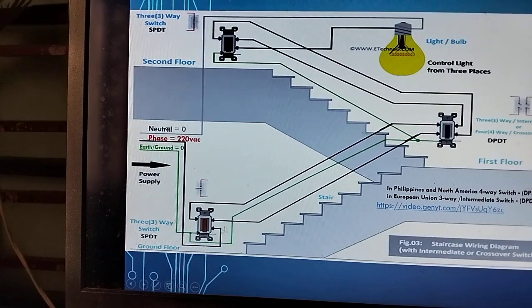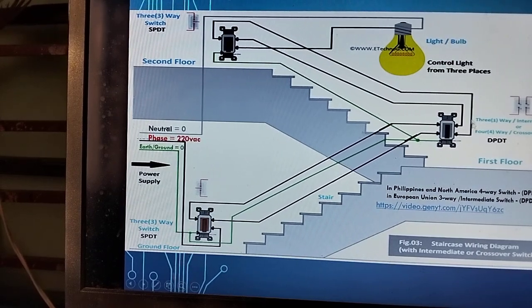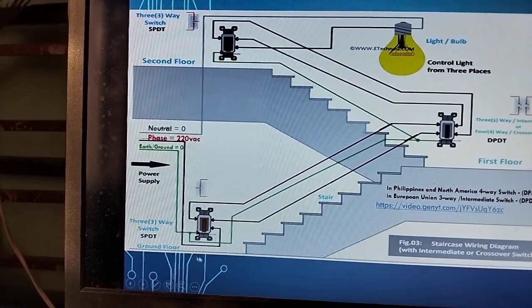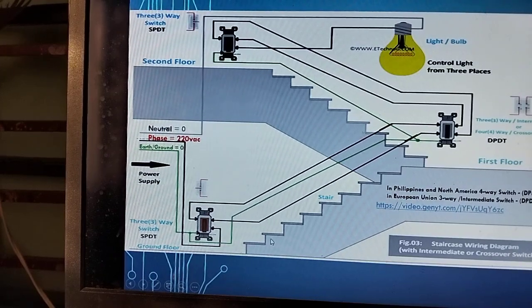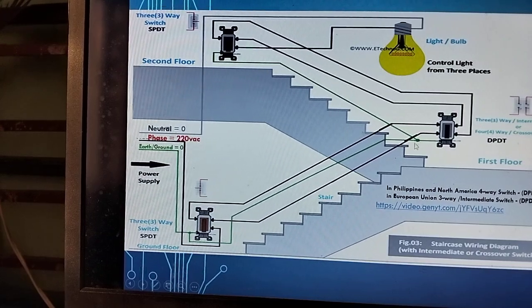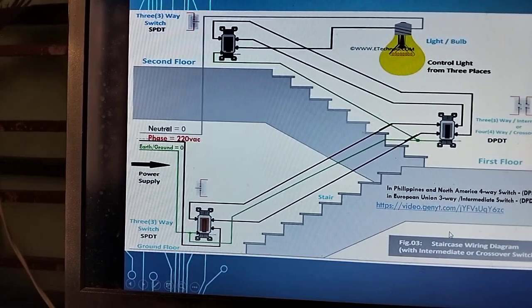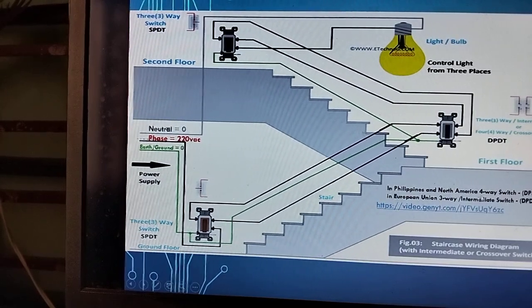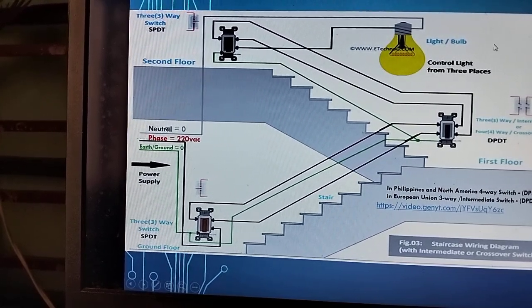For the travelers. Usually they are used in a 2-story or 3-story building. If you have a 3-story building, then you must use the 4-way switch. By the way, here in the Philippines, we call it a 3-way switch and a 4-way switch. Whereas in the European standard, the 3-way switch is called a 2-way switch, and the 4-way switch is called an intermediate switch. That is the difference. If you apply as an electrician abroad, particularly in Europe, you must follow their standard, even the terminology of the electrical components and the standard rules.